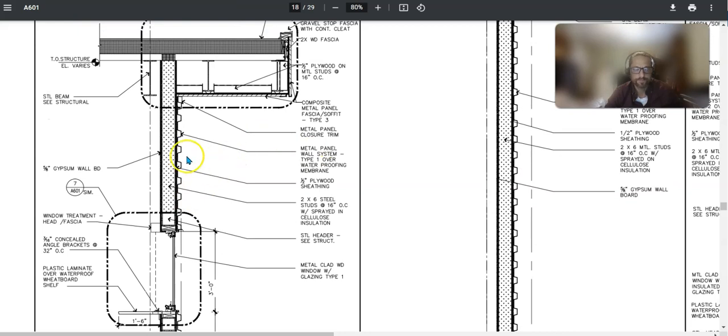But here we go. You can see here we have the wall construction, right? So some 5/8 gypsum wall board, that's an indicator that obviously it's inside, right? And then we have this layer, this layer, this layer. I'm going to let you sort of go through the information here to figure out those layers. Okay, but that tells you all the layers of the wall. And then you just need to find the R value on the R value charts that are provided and add them up. So the total R value of this wall is going to be the inside air layer plus this layer plus this layer plus this, right? So you take all those R values, add them up, and that gives you your total R.